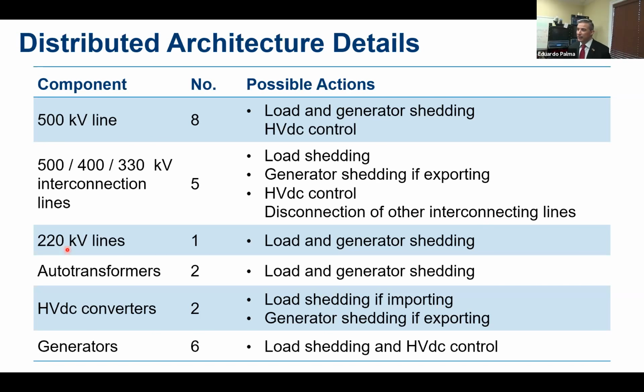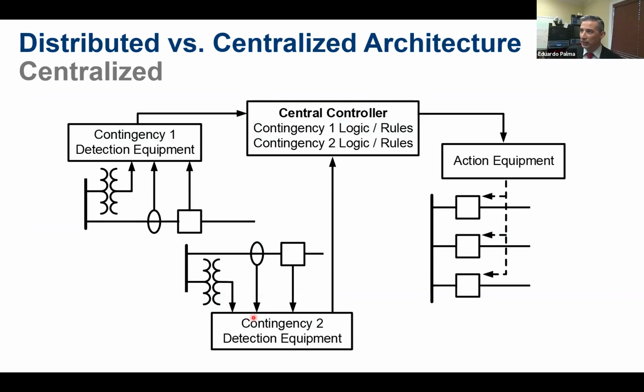Let's talk about centralized. Centralized means that there will be some logic on the devices that are hardwired to these currents and voltages and status of the power system that are remotely in the 500 kV substations, but they all report to one central controller. The central controller allows flexibility of adding more security and more lines of code in order to take into consideration more contingencies. Because in a central controller, we not only take into consideration the devices that are distributed in the power system, but we can complement this information with information from SCADA or the information that the operators received.